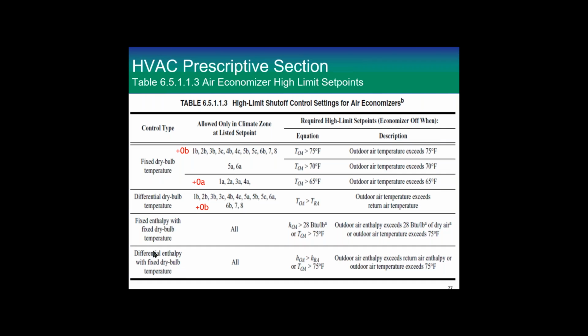Now, there's a lot of debate about enthalpy in the standard, in the working groups, because enthalpy controllers that are good, that give you good results consistently, are very expensive, and we can't afford to require them for the paybacks. But in real life, if you're using a lot of economizers and you're using enthalpy for a lot of your control loops, then you should at least once, and you can share it in some weather station or something, get a good enthalpy controller, which costs several $1,000s.